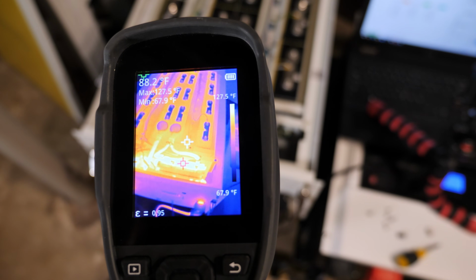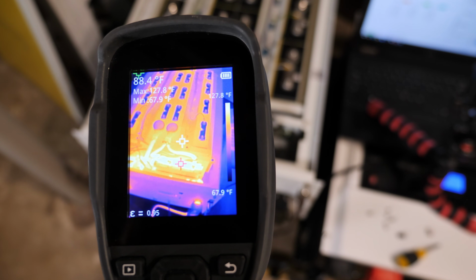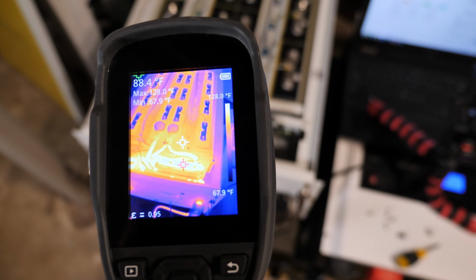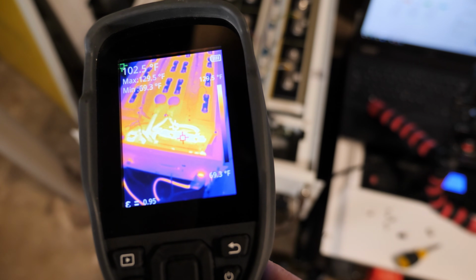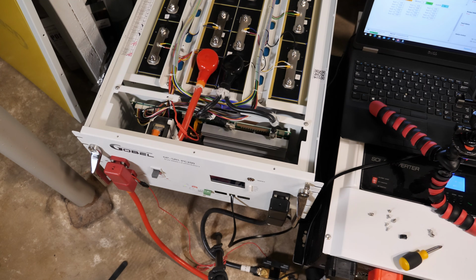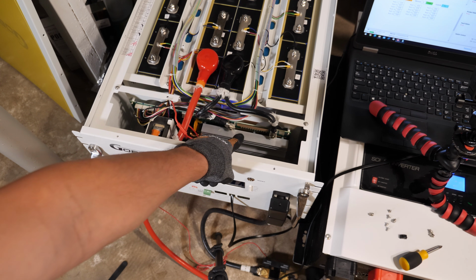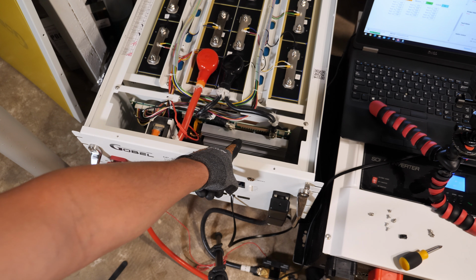Hottest spot that's showing up in there is around 127 degrees, and that's going to be the BMS, it looks like. You can see the red piece moving around, that's just the automatic hotspot tracking. That heat sink right there is basically 128 degrees Fahrenheit.